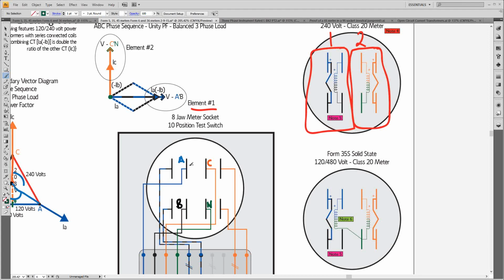Okay, so this is how it's wired. This is the meter sitting in. I'm going to replace it with the 35S. So I pull up the 5S electromechanical. I plug the 35S into this, and the 35S, because it's an auto-ranging meter, the potential coils in the 35S, just like it was with the 3-phase 3-wire delta, are both connected to one point in it. Okay, that instead of coming down and being connected here, in the 35S, there's nothing connected to this terminal in the meter itself.